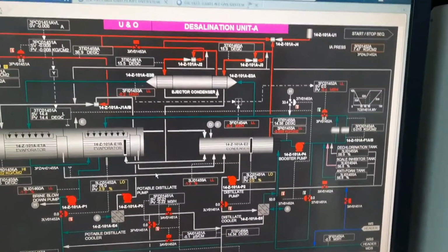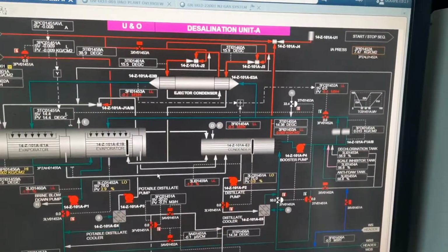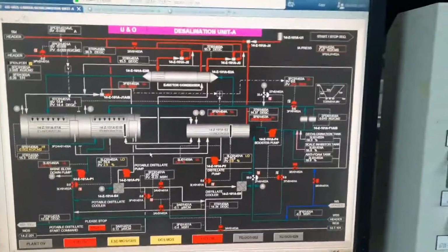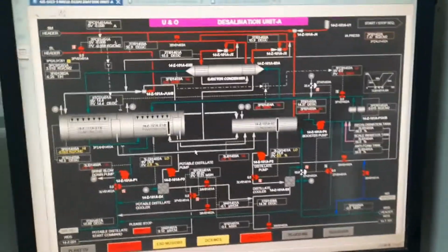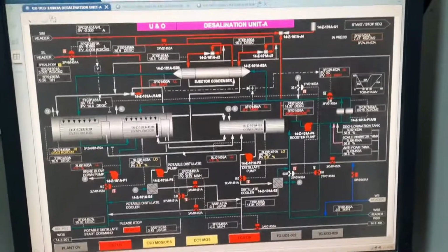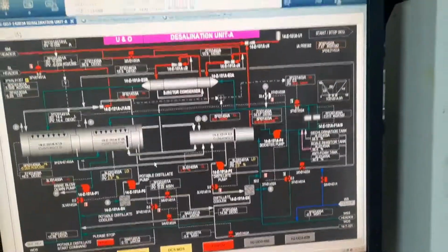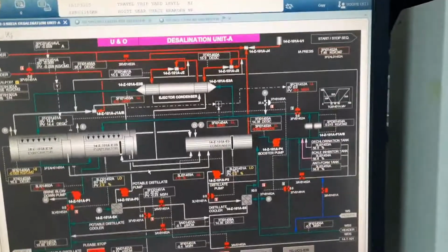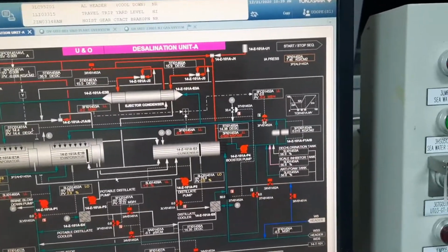To remove the calcium sulfate scale, we need to dose EDTA. The chemical dosing is the same process. Only remove the acid container and bring the EDTA container to this side. Water circulation starts, the pump pulls up the vacuum and the temperature increases, then EDTA dosing starts, same process.